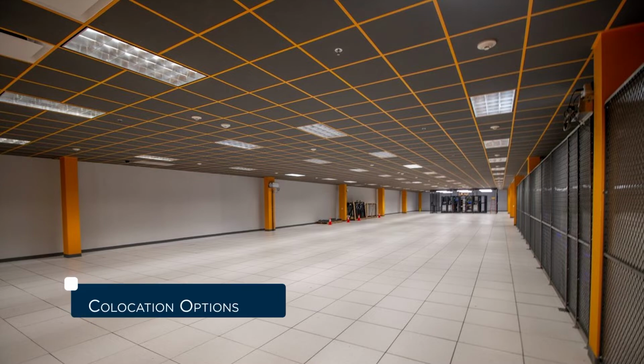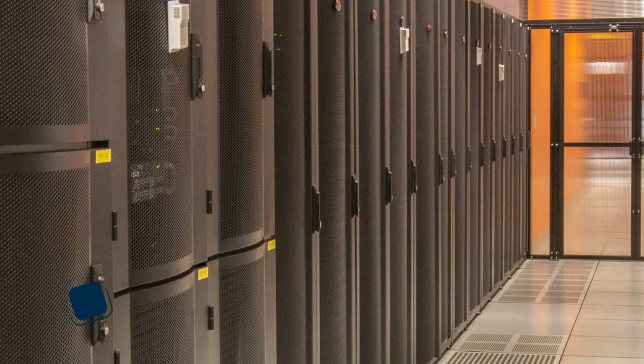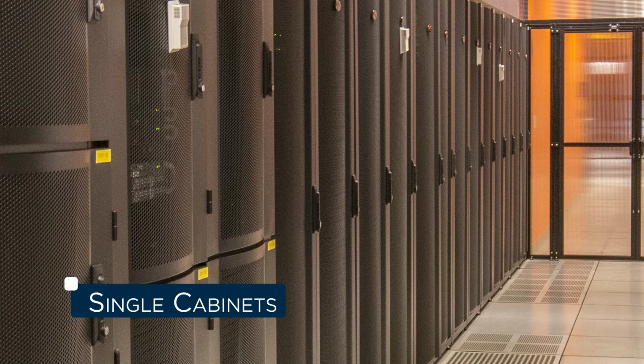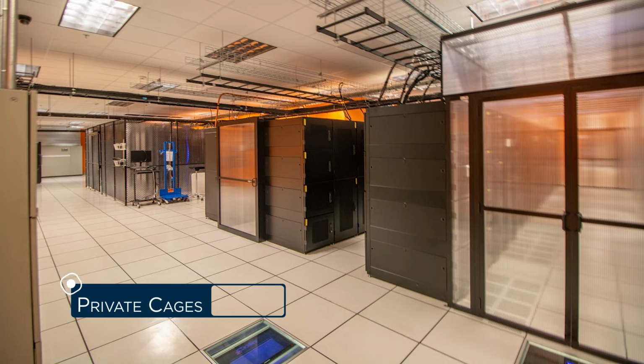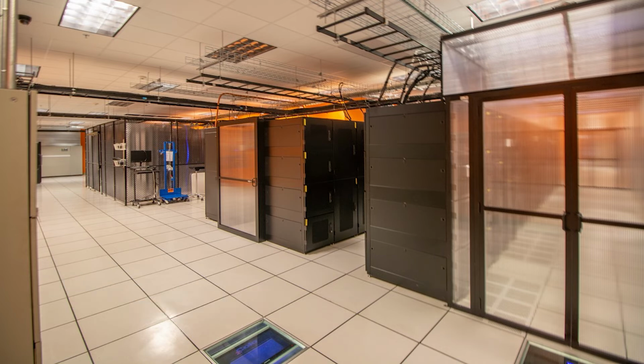DataBank provides several co-location opportunities at this facility: single cabinets, cages, and private suites. The common area is for single cabinet customers and will support up to 5 kilowatts. The cage area and private suites support up to 15 kilowatts of power per cabinet footprint. All customer areas utilize a traditional cold aisle, hot aisle configuration.